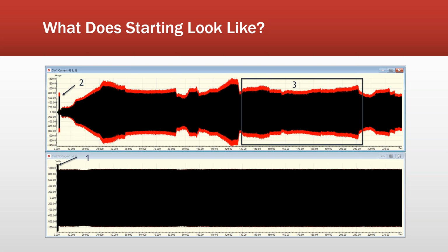That could be years. So right now we're seeing an average before we go to a site. If a site has a lot of variable wind conditions, I'll show that in a second, based on our history now, we put in an extremely accurate estimation of how many towers we're going to find with different types of problems. So this 2 right there, that is an impulse from when the breaker closes. So I have voltage down below, and then the breaker closes, and that causes that shock in the system even before the soft start. And it doesn't matter whose design it is.